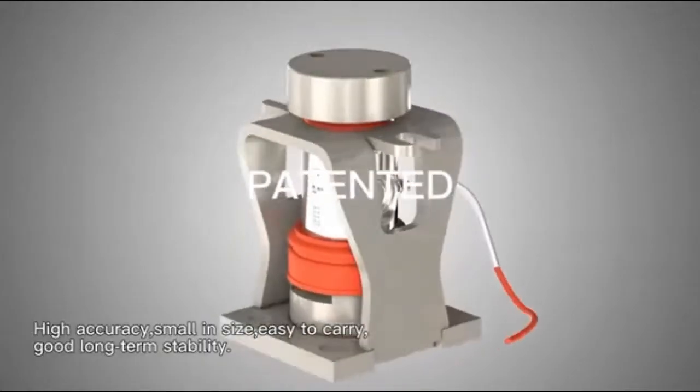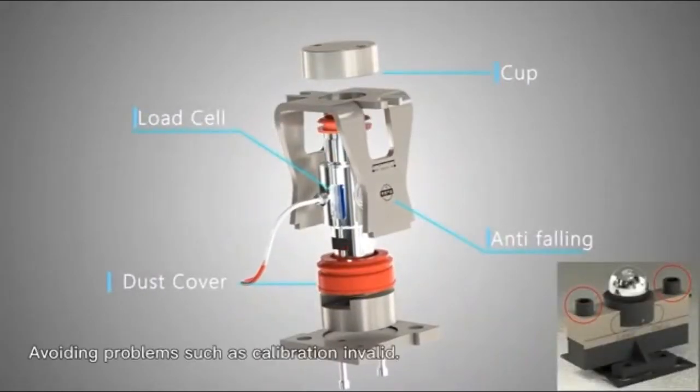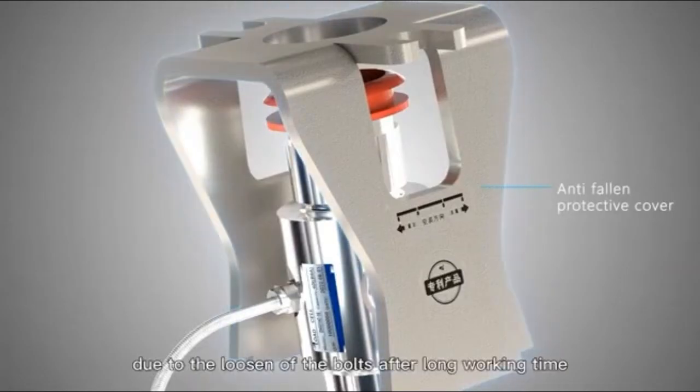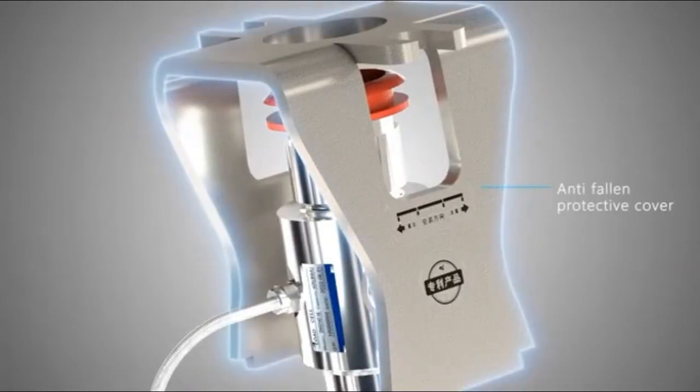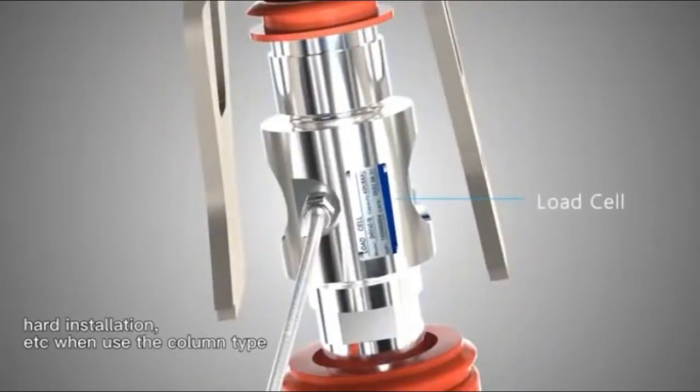The small size makes it easy to carry with good long-term stability, avoiding problems such as calibration becoming invalid due to the loosening of bolts after long working time. It solves the problems of falling down, swiveling, and hard installation that we see with column type load cells.